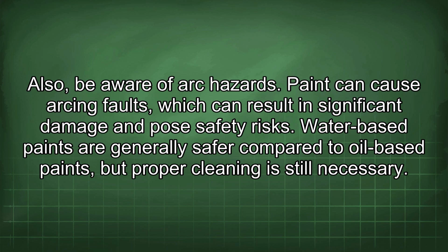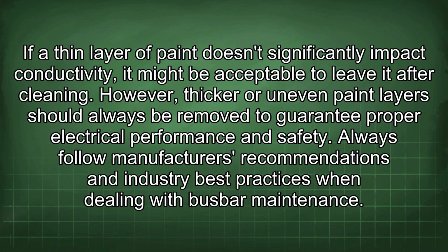Water-based paints are generally safer compared to oil-based paints, but proper cleaning is still necessary. If a thin layer of paint doesn't significantly impact conductivity, it might be acceptable to leave it after cleaning. However, thicker or uneven paint layers should always be removed to guarantee proper electrical performance and safety.